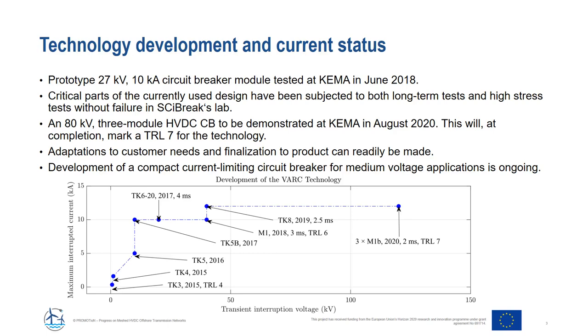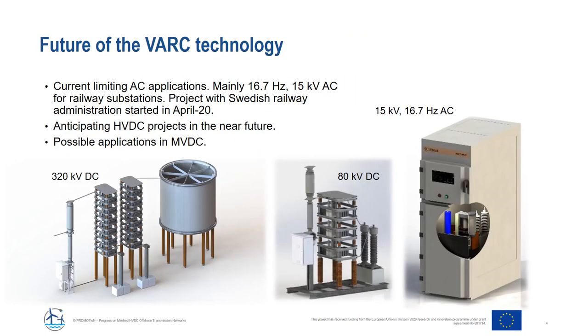This most recent test marks TRL 7 of the technology. The VARC technology is now ready for deployment in an HVDC grid — both the technology and the basic circuit breaker design are ready. The next step is likely a pilot installation. DC circuit breaker technology can also be applied for AC current limiting applications. SCiBreak has recently been awarded an order on current limiting circuit breakers for railway feeding applications in Sweden on a single-phase 15 kV 16.7 Hz grid. After successful deployment in medium voltage AC applications, acceptance of the VARC in HVDC markets is expected to follow.